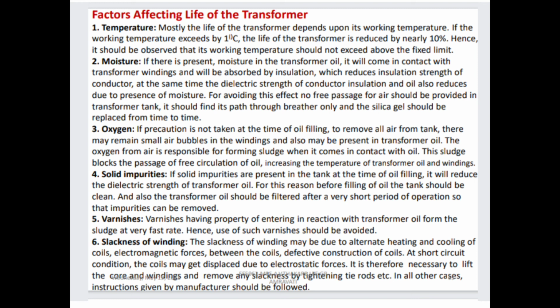Means their working temperature, it is very important for the life of the transformer. Next is the moisture. If there is moisture present in the transformer oil, it will come in contact with the transformer winding and will be absorbed by the insulation, which reduces the insulation strength of the conductor. At the same time, the dielectric strength of the conductor, insulation and oil is reduced due to the presence of moisture. For avoiding this effect, no free passage for air should be provided in the transformer tank. It should find its path through the breather only, and the silica gel should be replaced from time to time.